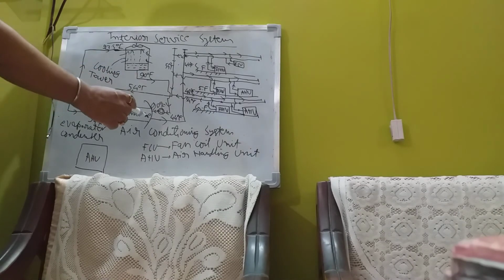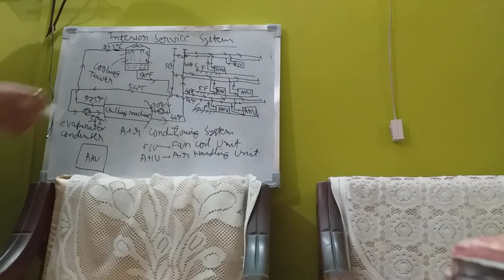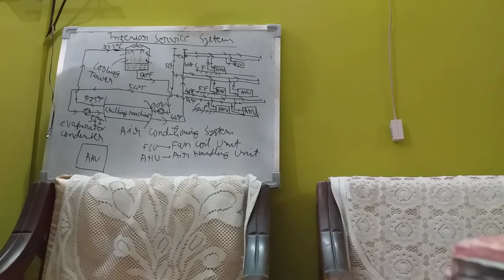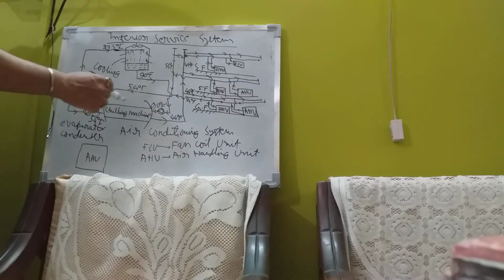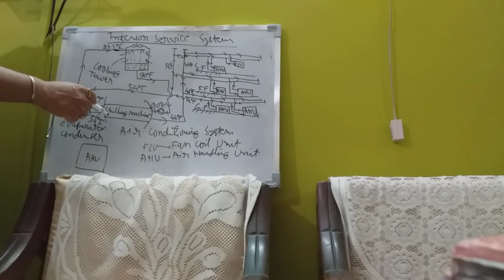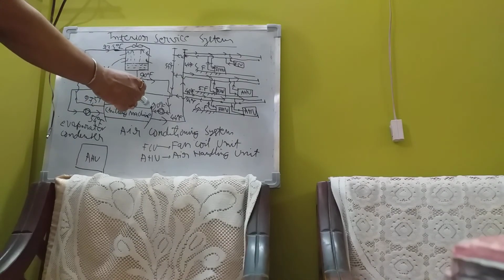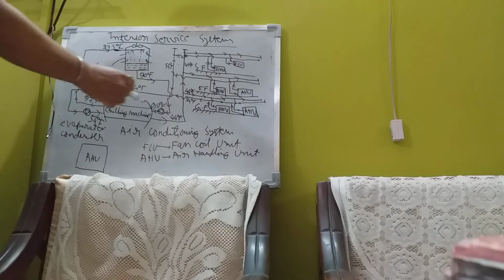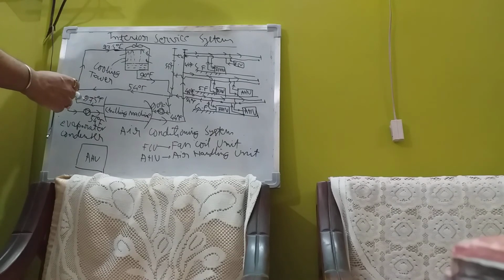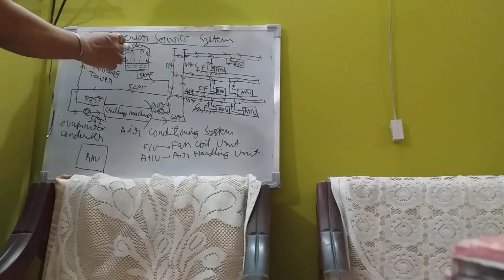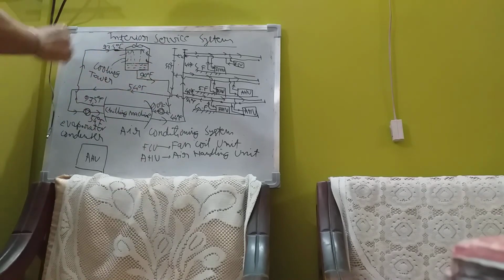The condenser of the chilling machine contains refrigerant vapor at high temperature, which is in vapor state. That gets cooled because of cold water at 90 degree Fahrenheit and becomes liquid refrigerant. That goes through the expansion valve to the evaporator. But this water picks up heat from the refrigerant gas at 90 degree Fahrenheit and becomes 97.5 degree Fahrenheit, and at 97.5 degree Fahrenheit it comes here and again falls and gets to 90 degree Fahrenheit, and the cycle continues.